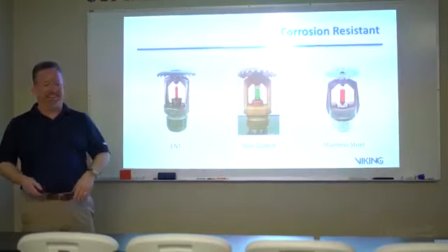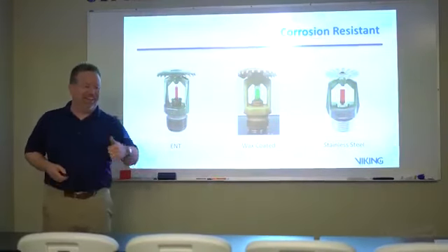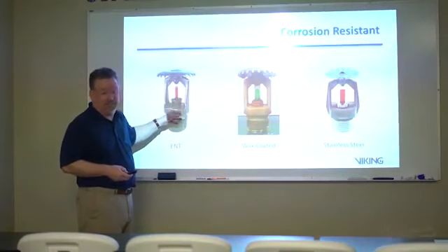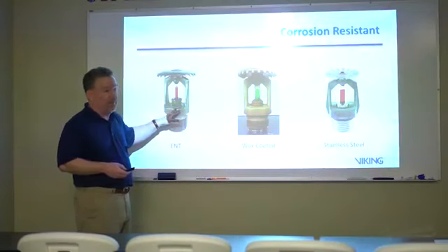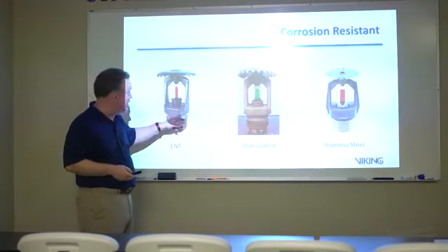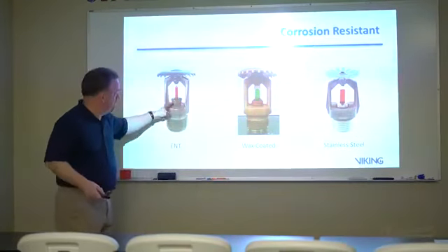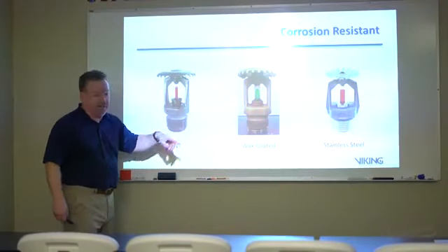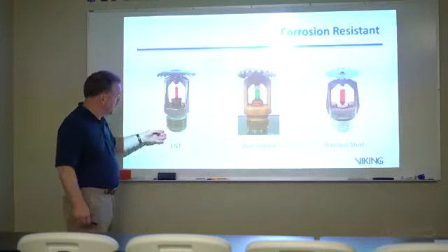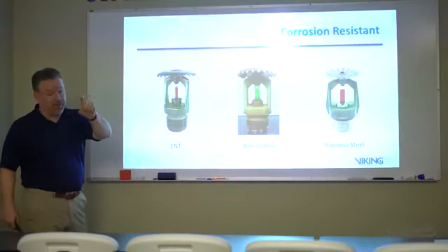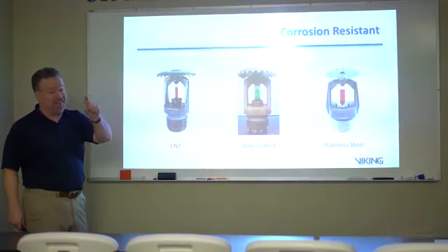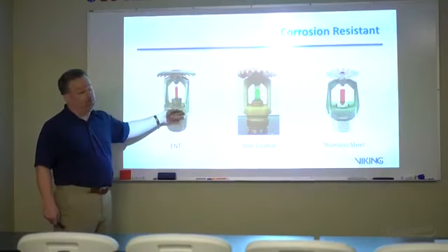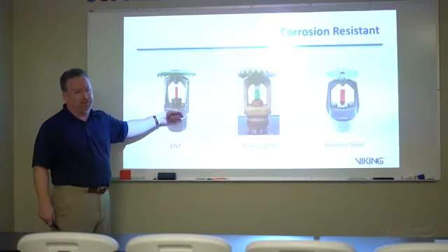So we're going, hey, wait a minute, that's not a manufacturing issue, and it's not an exterior corrosive issue, because this was in a light hazard occupancy area. I think it was a daycare center or something along those lines, but it was goobering up our pip cap and everything right in this area. So we basically took that particular sprinkler because they needed to replace it with an exact replica for spacing and everything else. And we were able to, because we've just started offering this within the past couple of years.